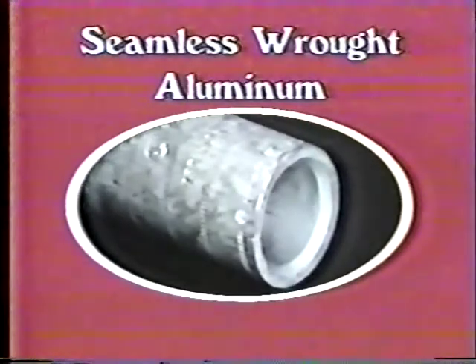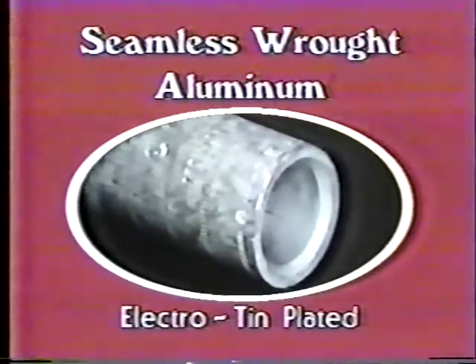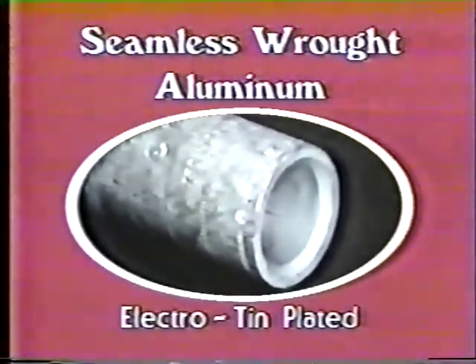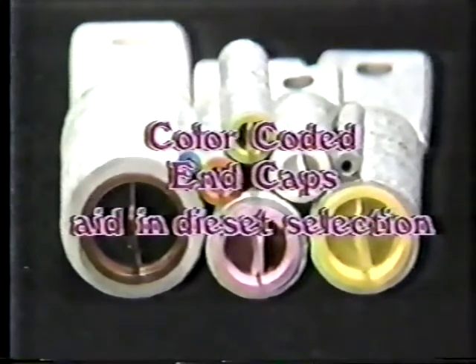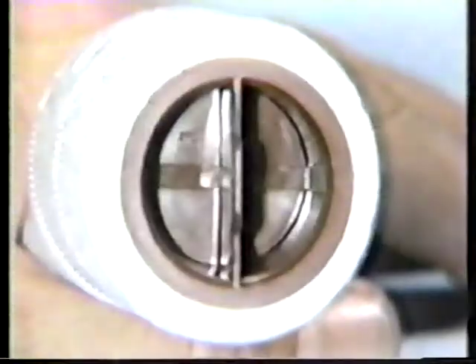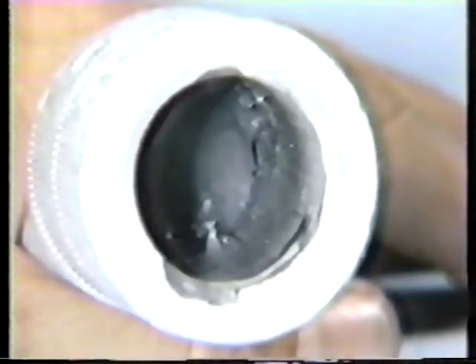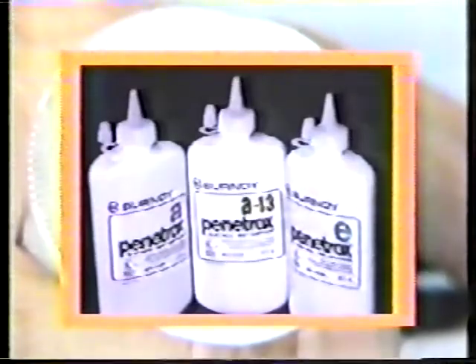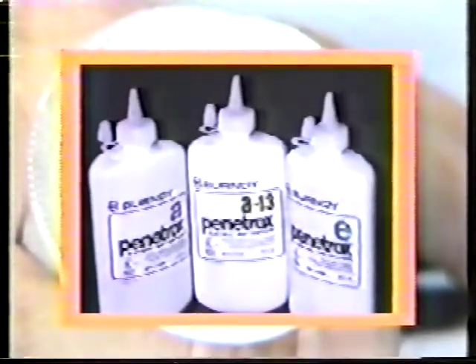Burndy's aluminum connectors are made from seamless wrought aluminum, which is electro-tin plated to prevent corrosion. They are UL listed and clearly marked with the wire size, die index, the position and number of crimps required. Color-coded end caps are used to aid in selecting the proper installation die set. And all aluminum terminals and splices are pre-filled with Burndy's unique Penetrox compound to enhance conductivity and prevent oxidation.